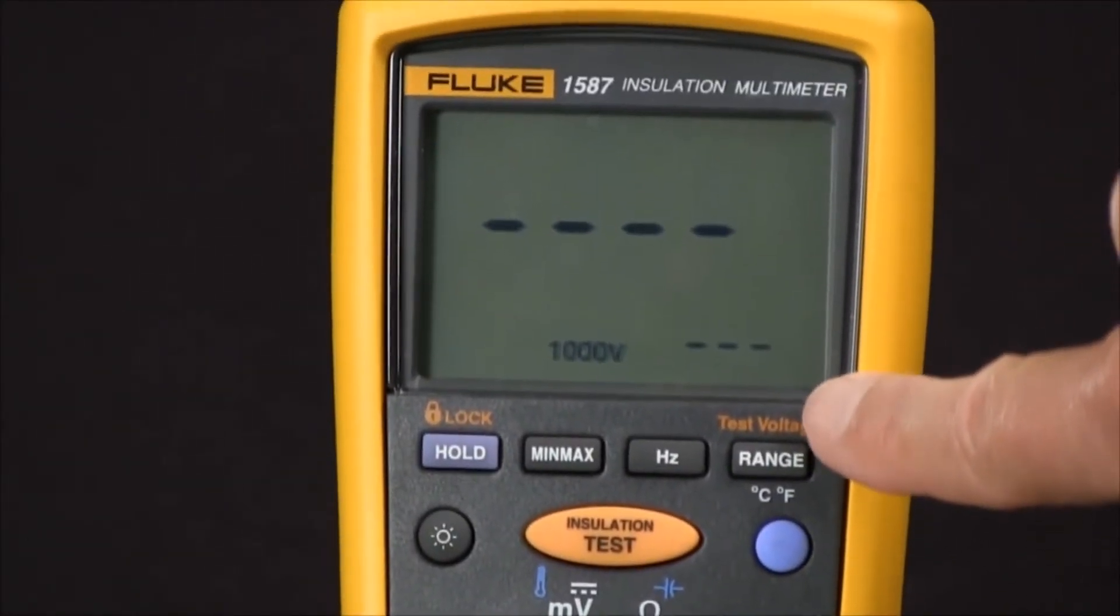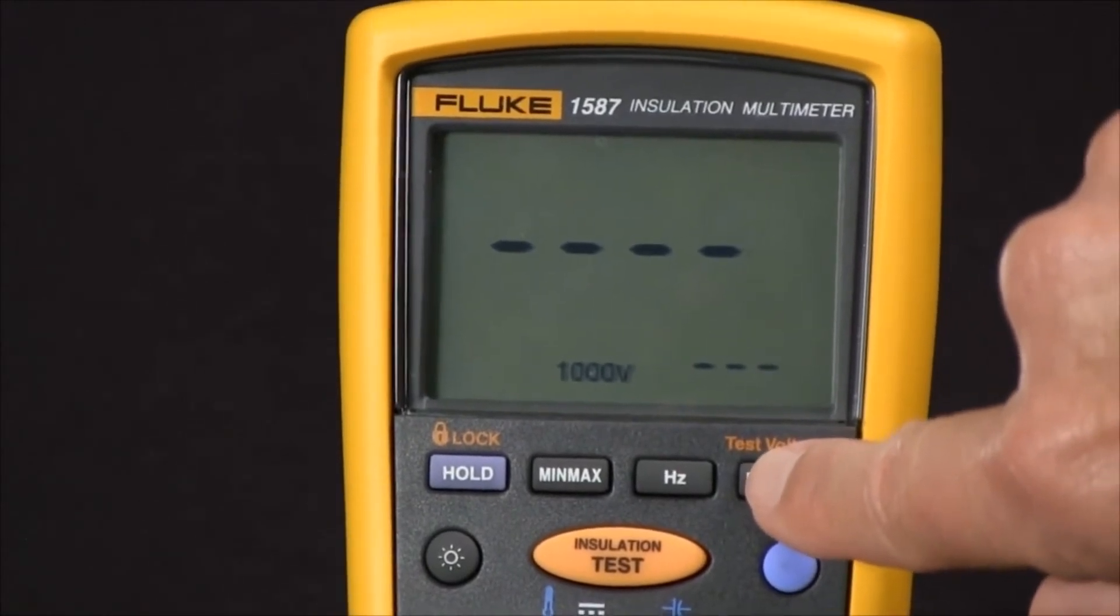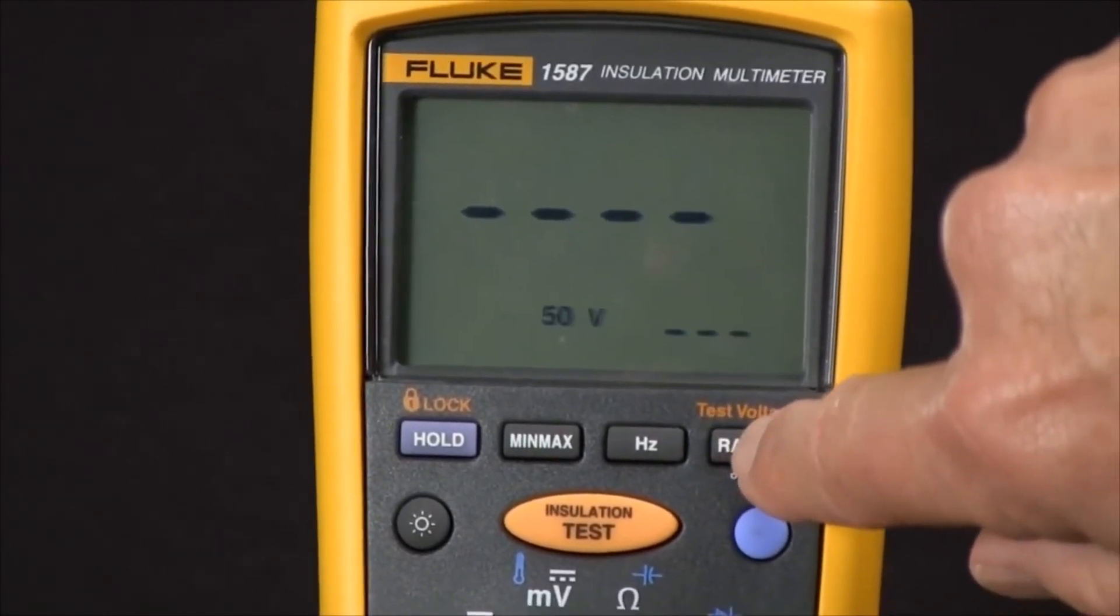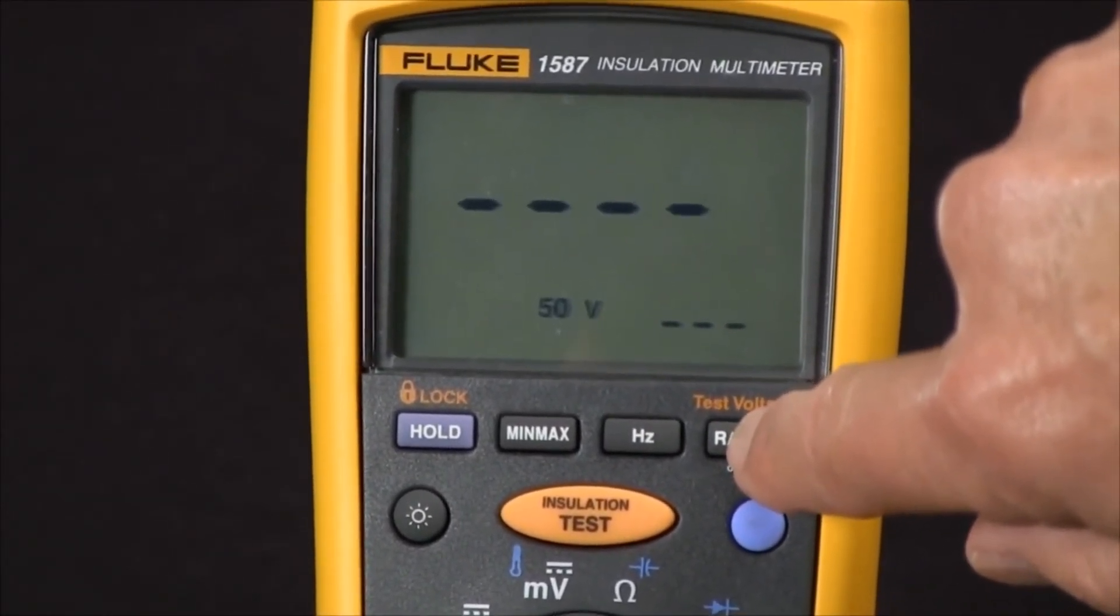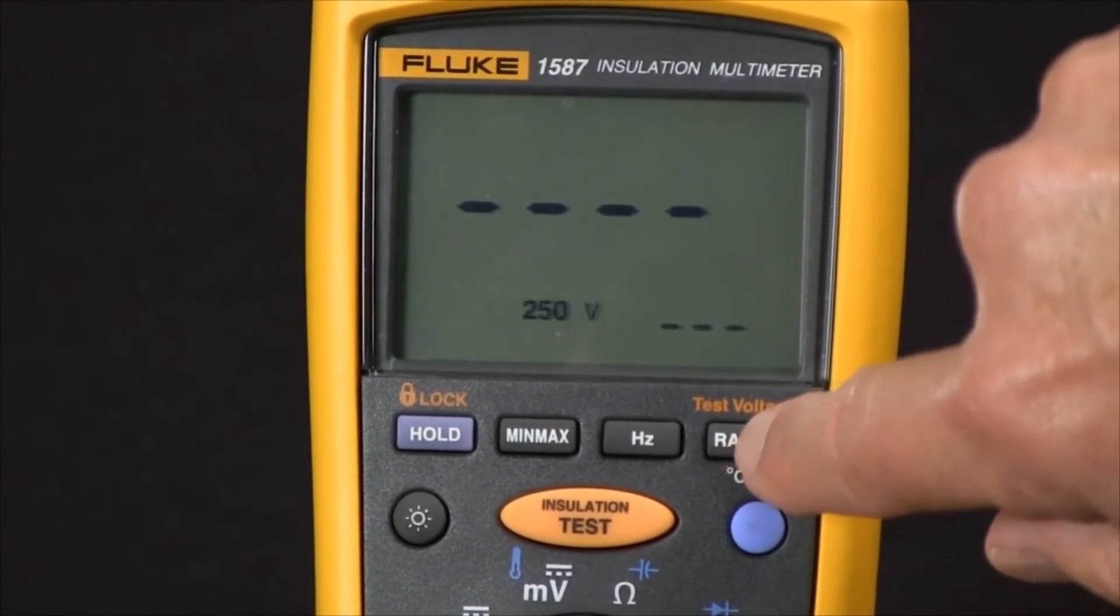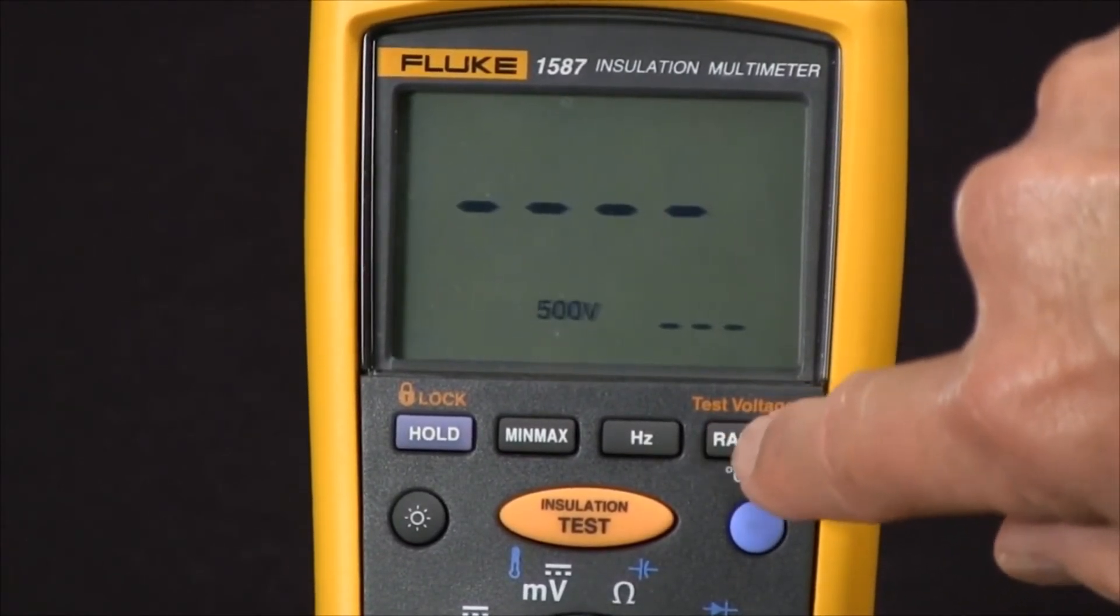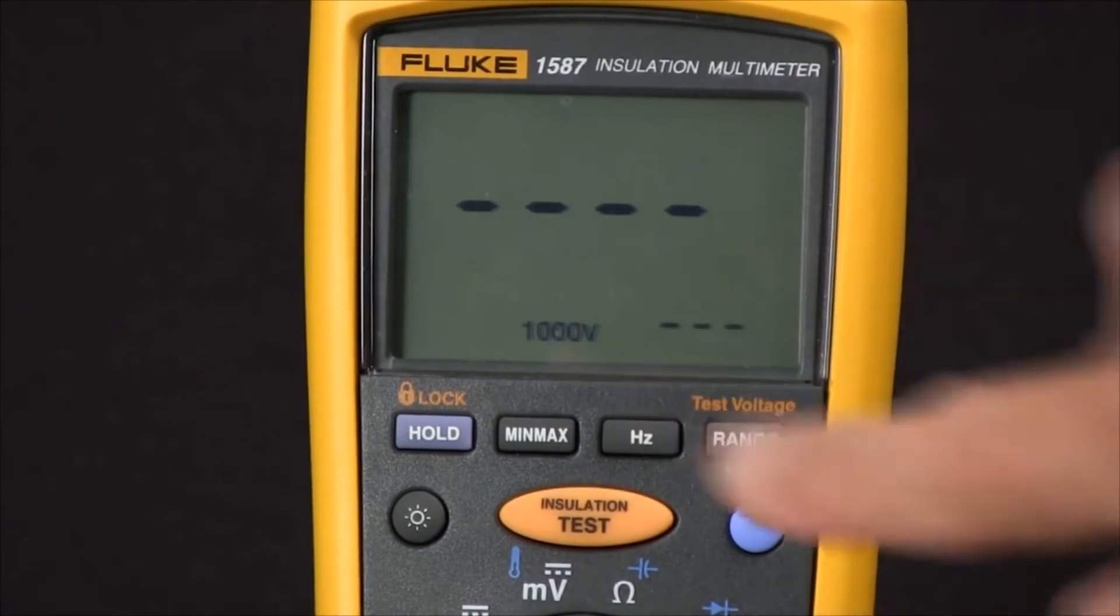And at this point we can select the test voltage by pushing the test voltage button. Every time we push it we rotate through 50 volts, 100 volts, 250 volts, 500 volts, and 1,000. I'm going to use 1,000 volts.